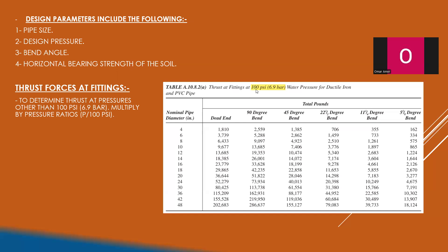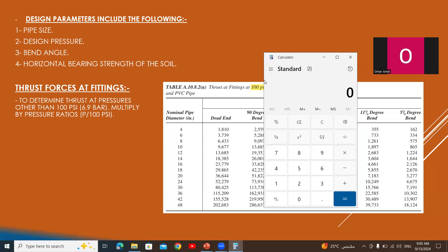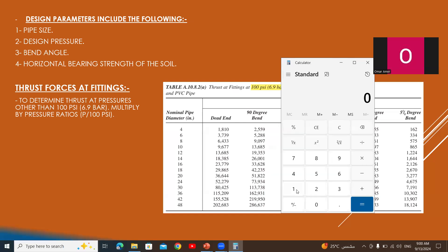An important note: this tabulated value is for a design pressure inside the pipe of 100 psi, equivalent to 6.94 bar. If we have a different pressure value, we must multiply by a ratio between the pressures. For example, if the pressure is 120 psi, we take the value 13,685 and multiply by the ratio of 120 to 100. So the thrust force will increase to 16,422 lb, as pressure increases the thrust force.